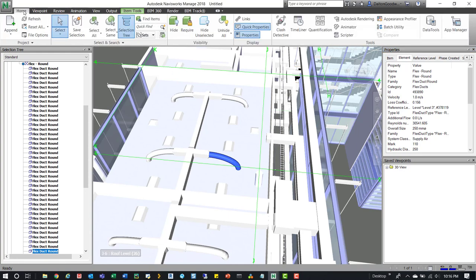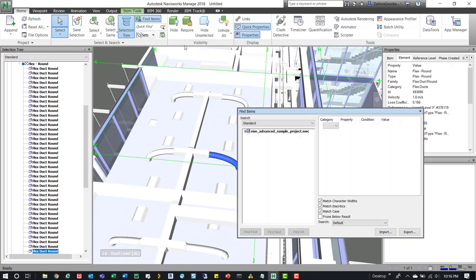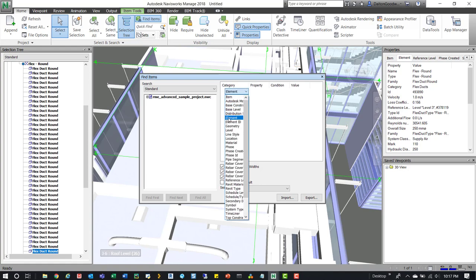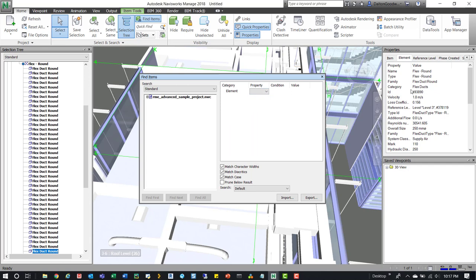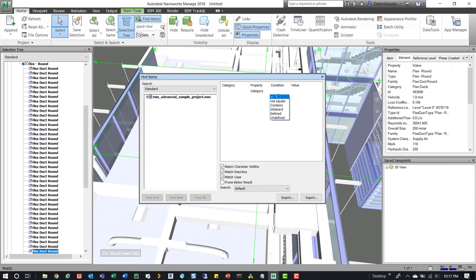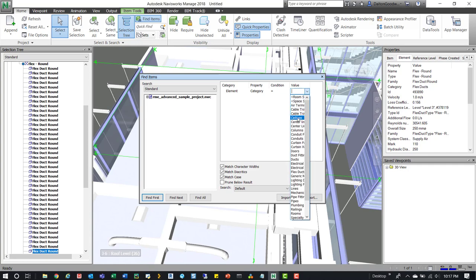We'll start with the Category for flex ducts. Go up to the Home tab and click Find Items. With an element selected, we can start setting it up. We have Category, Property, Condition, and Value. The first category is going to be Element — I'll type 'E' to jump to it. Then for Property, press 'C' for Category and select it from the list. Set Condition to Equals, and for Value it should give us a dropdown. We look for Flex Ducts and type it out.